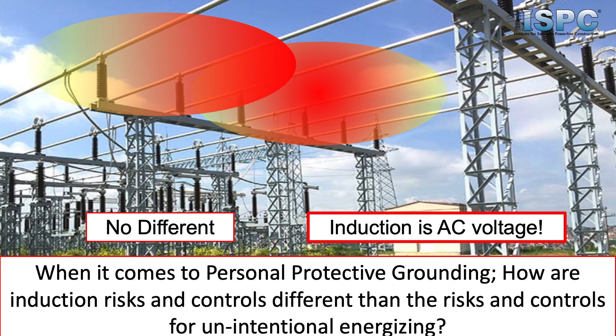You see a picture here of a wave trap installed on a downcomer in a 500 kV substation. Looks fairly innocent, right? The job for this day back in 2008 was to replace this wave trap. We were upgrading to a new wave trap, so the job for that day was to switch out of service, establish a protective work zone, apply grounding, apply bonding, and go up and replace this wave trap.